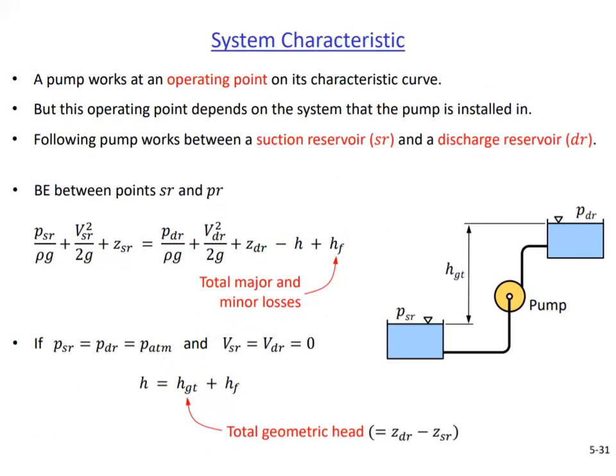Operating point of a pump is determined by the intersection of its HQ curve with the system characteristic curve. Let's learn how the system characteristic curve is determined. Consider a simple system with two reservoirs. A pump in between is used to pump water from the suction reservoir to the discharge reservoir. The elevation difference between the free surfaces of the reservoirs is called the total geometric head, and it is shown with HGT. System characteristic is obtained by writing an extended Bernoulli equation between the free surfaces of the reservoirs.